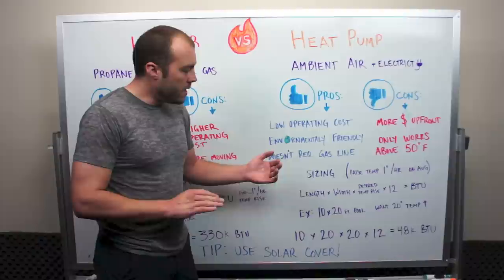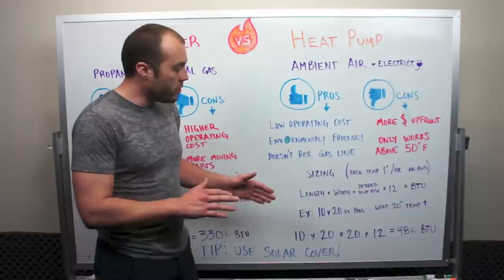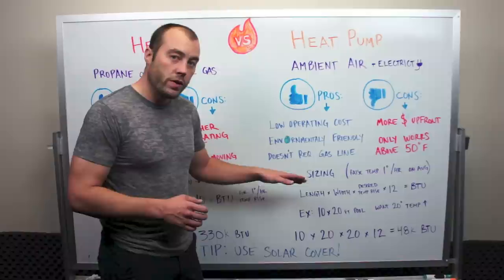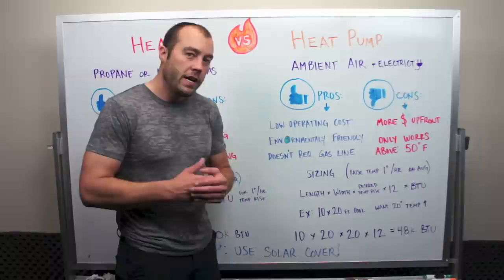Now let's take a look at sizing. For a heat pump, we're going to assume that we want to raise the temperature one degree per hour. The formula to figure out the recommended BTU is length times width of your pool times desired temperature raise times 12.